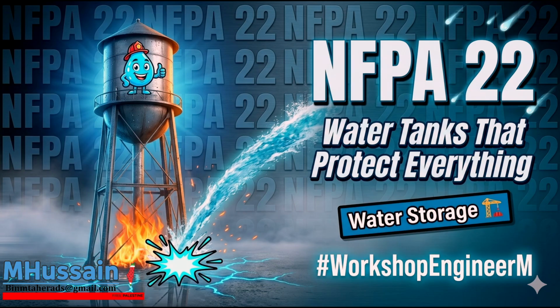Exactly. And you've specified the absolute best, most efficient centrifugal fire pump on the market. The engineering on your desk is just completely flawless. On paper, at least. On paper, yeah. But then, a fire breaks out in the facility. The heat detectors trip, the system kicks on, and it completely fails.